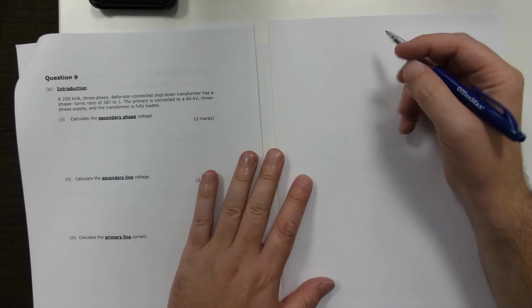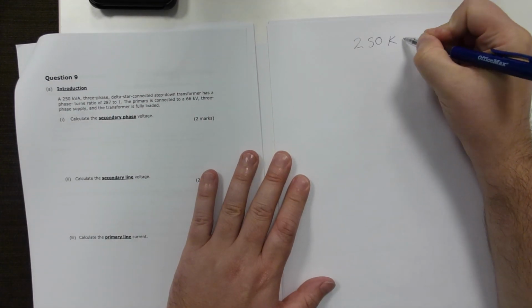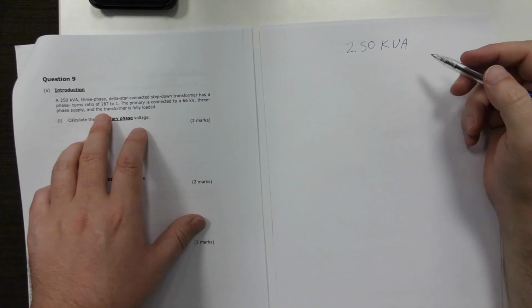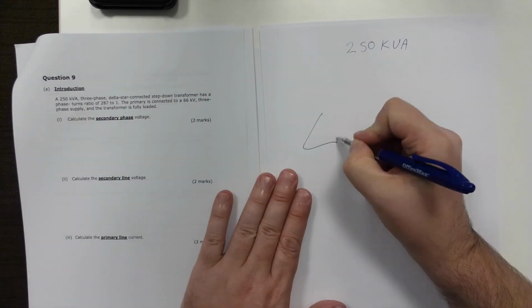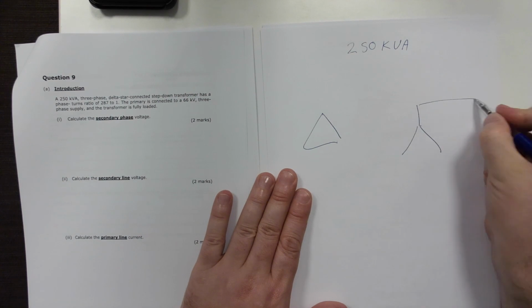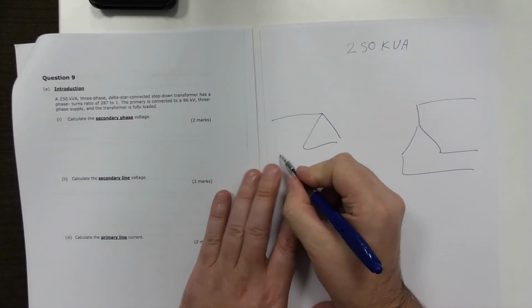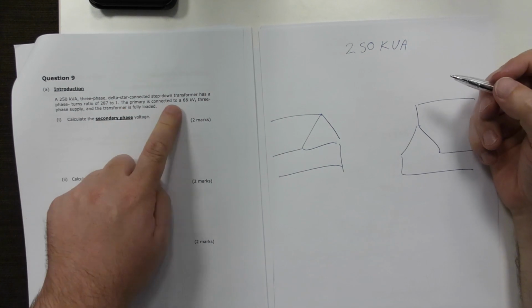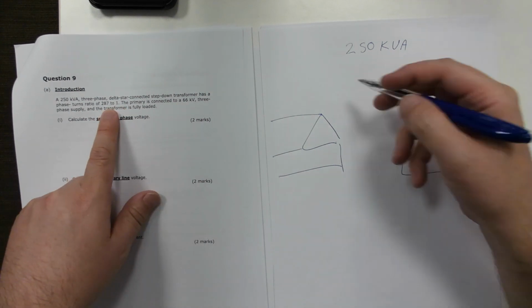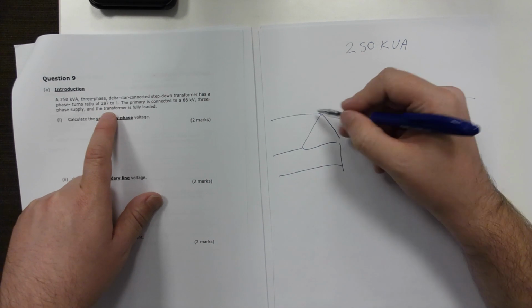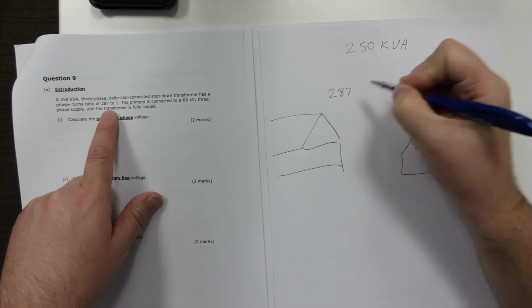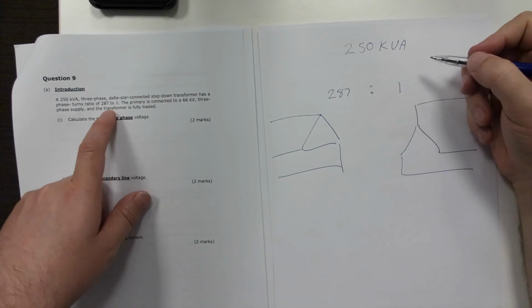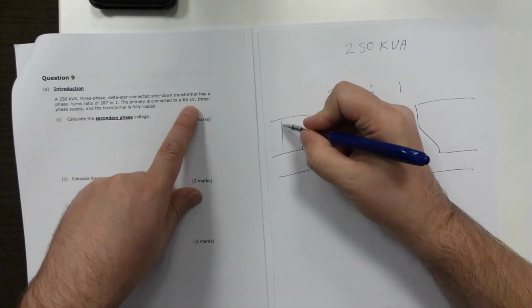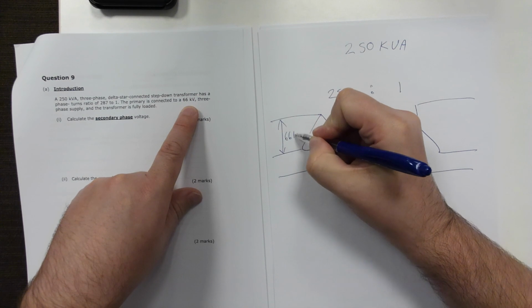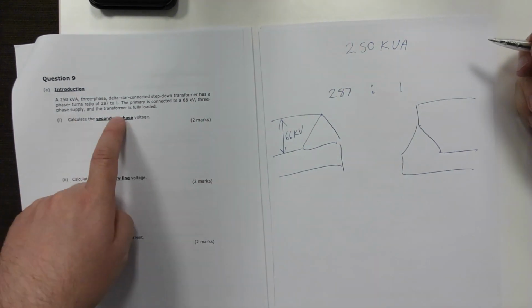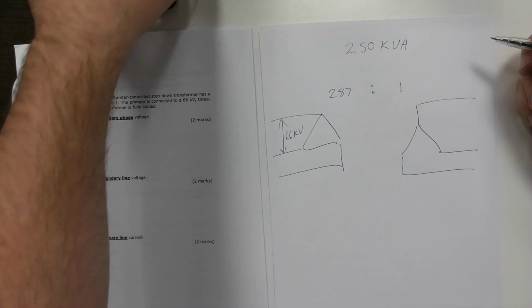So we have it is a 250 kVA, and then we have its delta star. So we have our delta, we have our star, and it's a step-down transformer. So left-hand side is the primary, 287 to 1. Primary is connected to 66 kV, 3-phase supply, fully loaded. Calculate the secondary phase voltage.